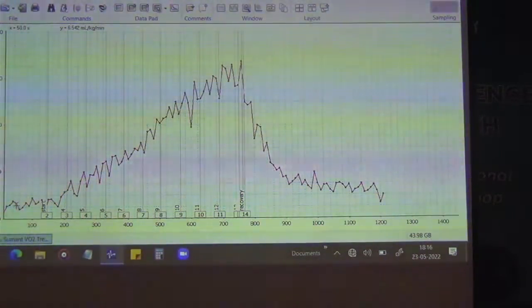Calibration is part and parcel of every testing. Now, if you are doing 20 tests in a single day, how many times will you calibrate? This may be a general question. We suggest calibrating one time, prior to the day's testing, and then you can proceed with the testing without recalibrating, until and unless there is any malfunction.